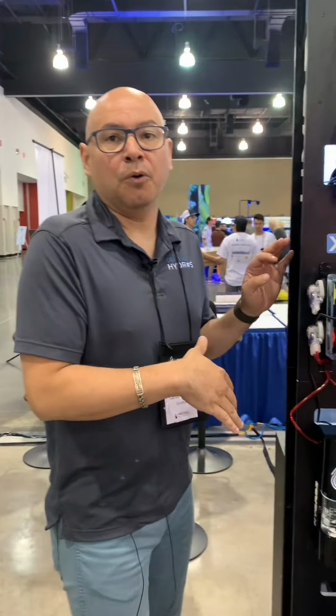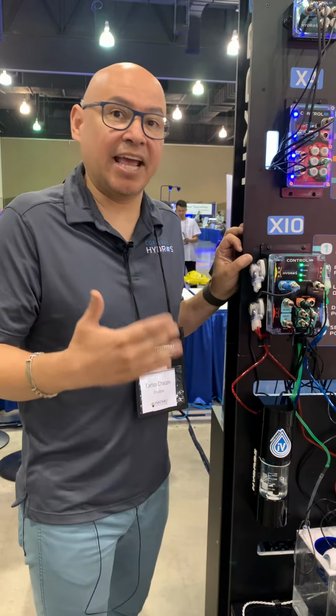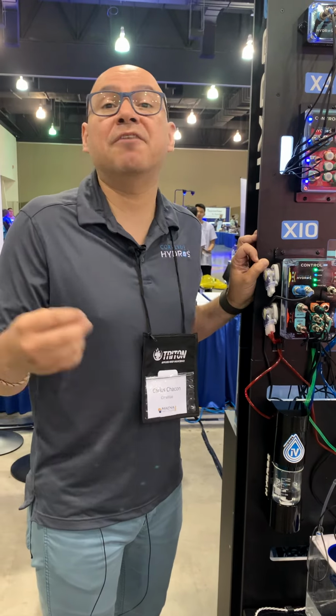They call it a K factor. A conductivity probe measures by having 2 plates with electricity going back and forth. The K factor is the distance between the 2 plates. Depending on what you're testing and how much dissolved organics you have in there, the conductivity changes. Other controllers out there use conductivity probes with a K factor of 1, which is meant for fresh water, while we use a conductivity probe with a K factor of 10, which is specifically made for salt water.